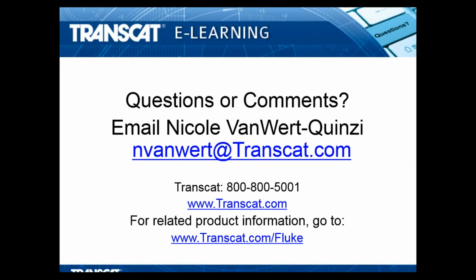Last question: can I use a reference probe when automating calibration with the 754? No, you can't. That's an important point with the 754 — I can connect one unit under test, I can't collect data from multiple units, and there's no place to connect a reference. So the only reference temperature you get is the indicated value on the dry block. You wouldn't be able to use, say, a 5626 to get a more accurate reading — you'd only get the reading from the dry block.